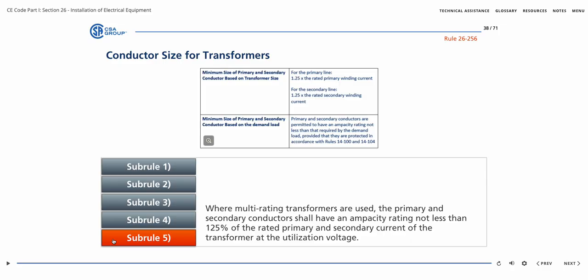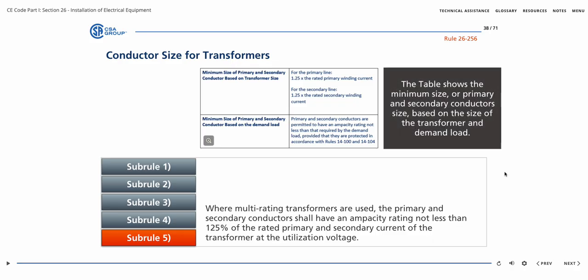Subrule 5 provides that where multi-rating transformers are used, the primary and secondary conductors shall have an ampacity rating not less than 125% of the rated primary and secondary current of the transformer at the utilization voltage. The table shows the minimum size of primary and secondary conductors based on the size of the transformer and demand load.